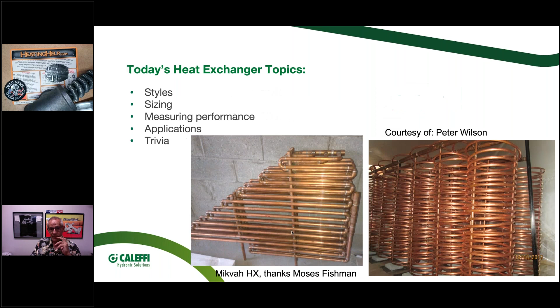Really, what it comes down to is the flat plate is probably one of the most efficient, just because there's a lot of surface area. They've really engineered these over the years, to the point where they can change the size and shape of the little chevron patterns. If you've ever cut one open, you've seen these plates - they can optimize the shape, the thickness of the plates, and the number of plates to really optimize performance. So of all the ones I've looked at, that claims to be the most efficient.